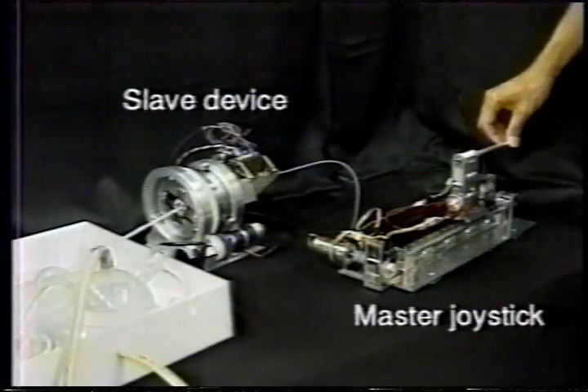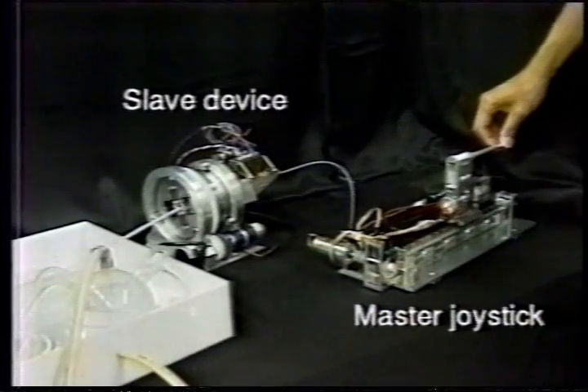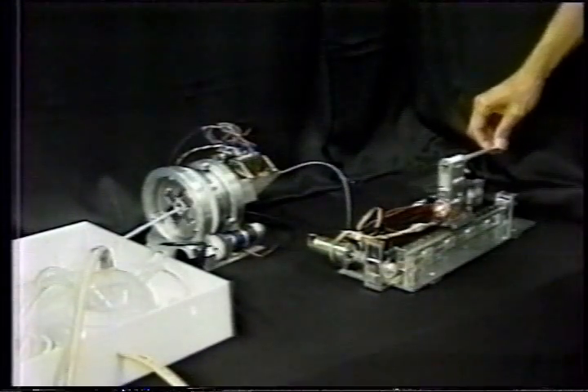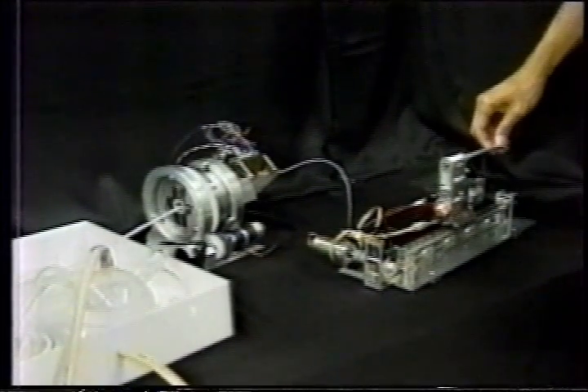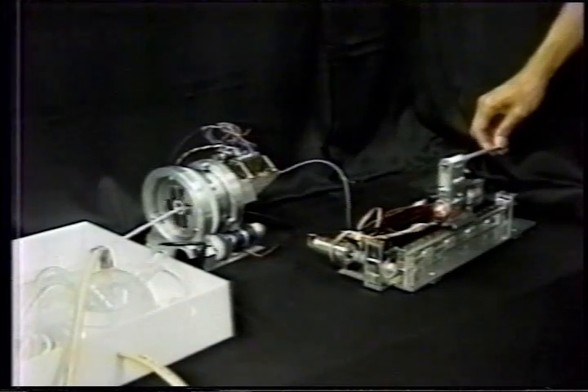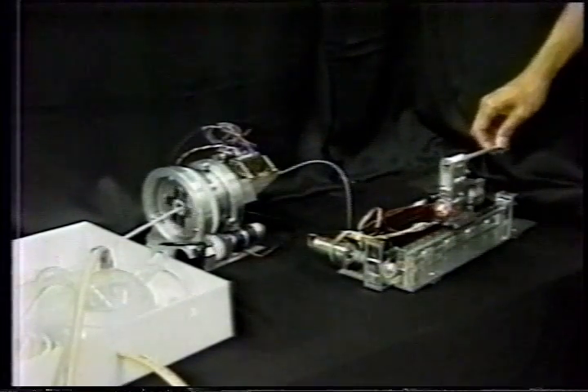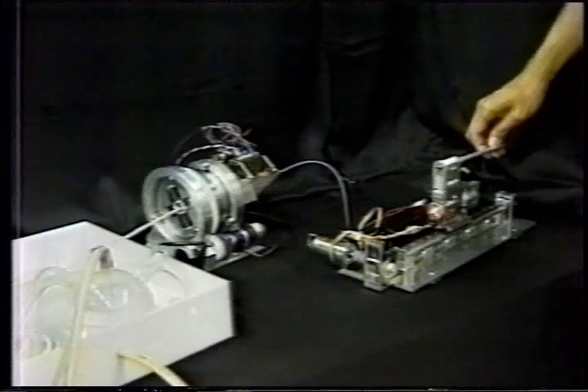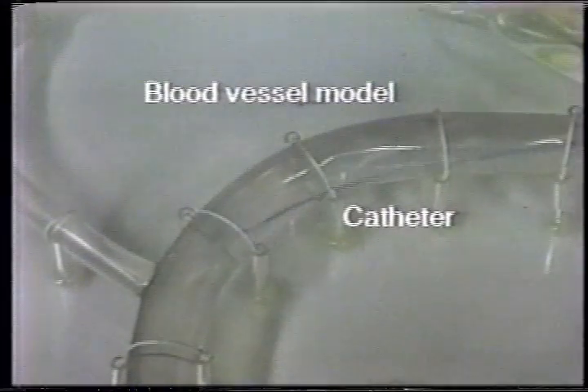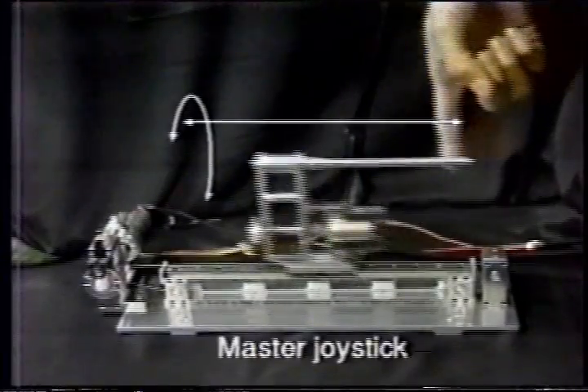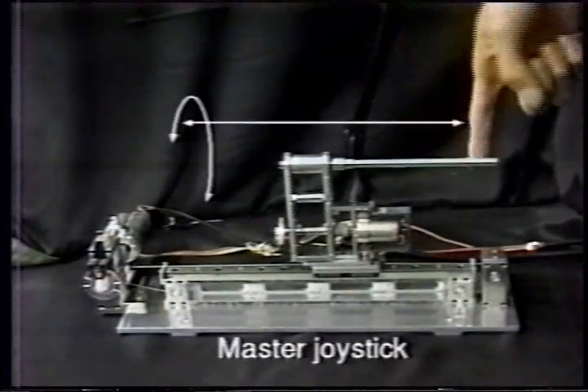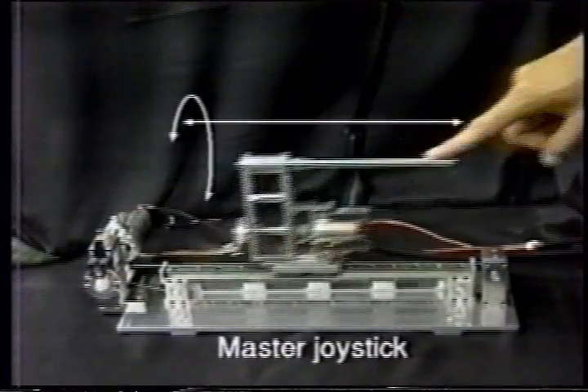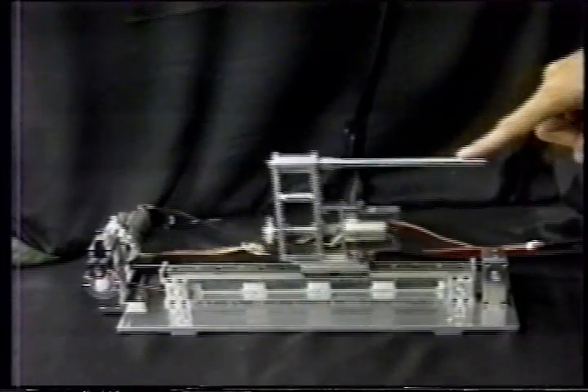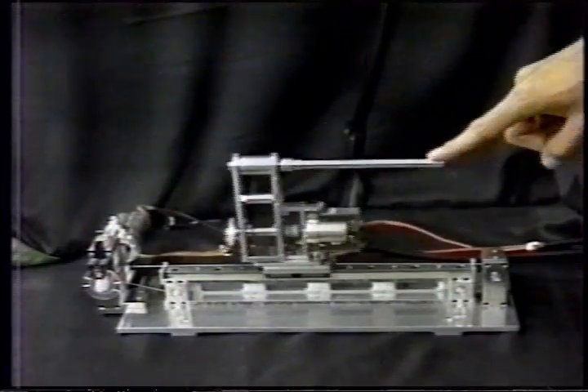The catheter manipulation system consists of a master joystick, which has very small mechanical impedance, and a slave device that follows the master movement well. The master-slave system has 2 degrees of freedom. The catheter is inserted into the blood vessels, and the treatment is performed. Each joint of the master joystick is connected to a DC motor by a wire. This mechanism realizes smooth motion and fine force display.